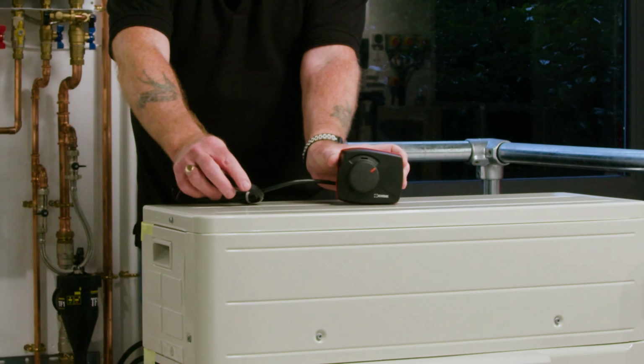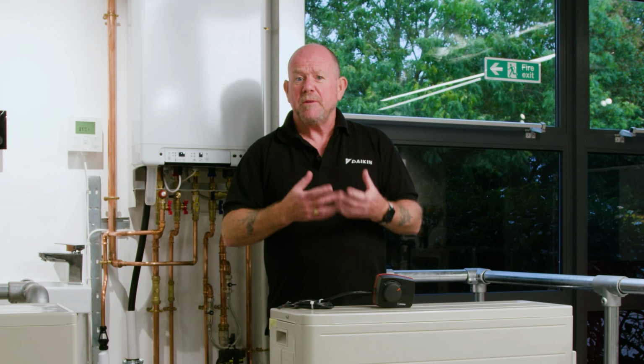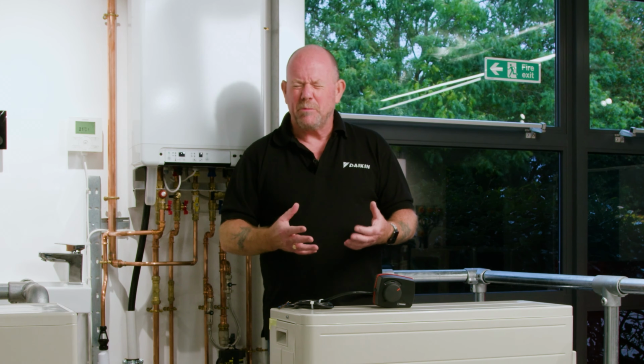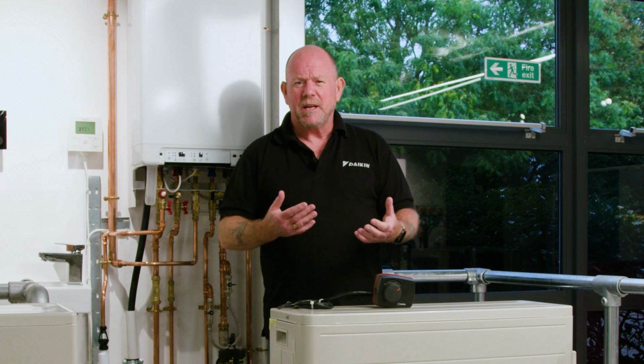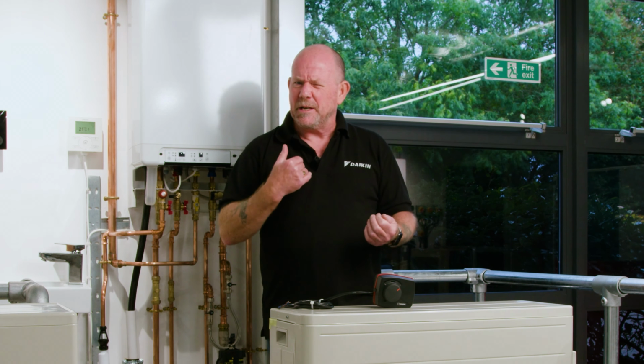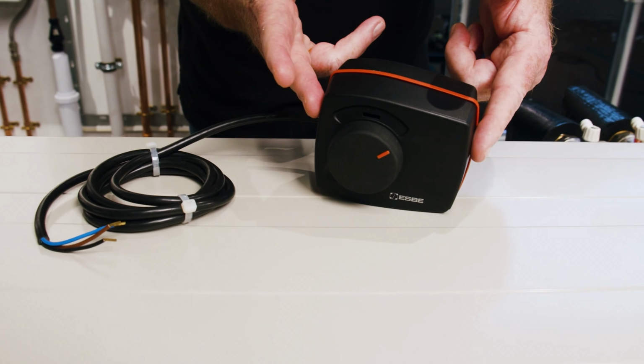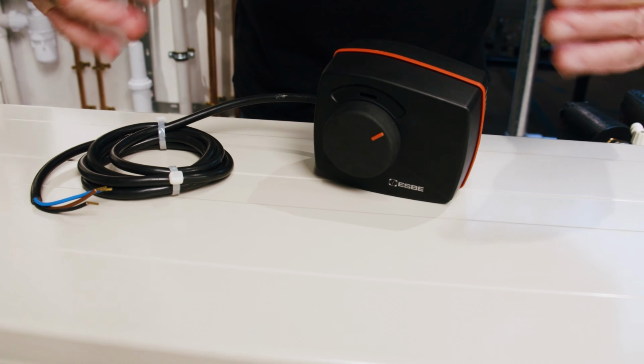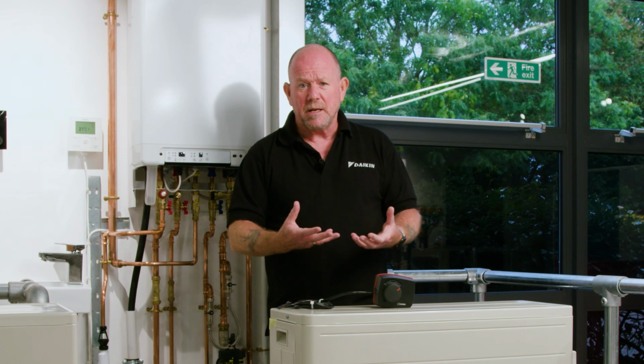As we've already heard, the system can be installed for instantaneous hot water, so with the boiler acting as a combi, or with stored domestic hot water. So in other words, we have a hot water cylinder. If we have a hot water cylinder, we're going to require a diverter valve. At Daikin, we use the ESBE diverter valve. The ESBE valve is a true diverter valve. And what a true diverter valve means is it can only do one thing at a time. It's a little bit like me. It will either feed the coil on the cylinder for domestic hot water production, or the radiators if heating is required.